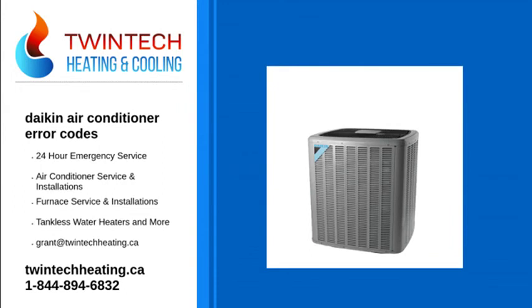Code AF. Result: malfunction of a humidifier system, water leakage of humidifier option, failure of swing float switch, improper drain piping incline. Code AH. Result: malfunction of dust collector of air cleaner, defect of dust collecting element, defect of high voltage power supply unit, stained insulator part, defect of indoor unit PCB.